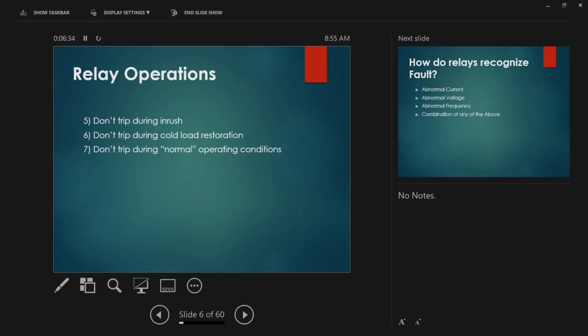Mostly that covers those parameters. Also, it should not trip during inrush current, because that's not really a real trip. The relay should understand that. Number 6, don't trip during cold load restoration. Don't trip during normal operating condition, which is very, very important. If you never have a proper setting, it might trip in a normal condition, which is not good.